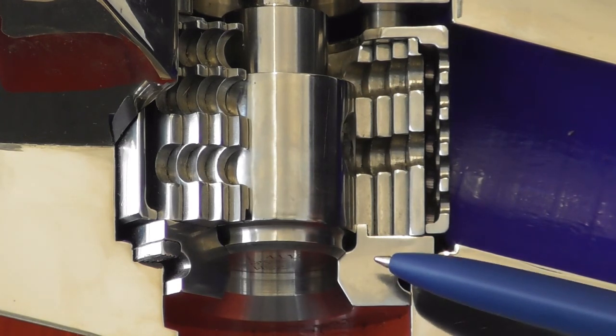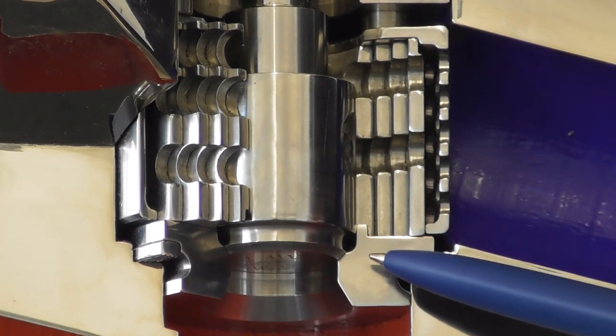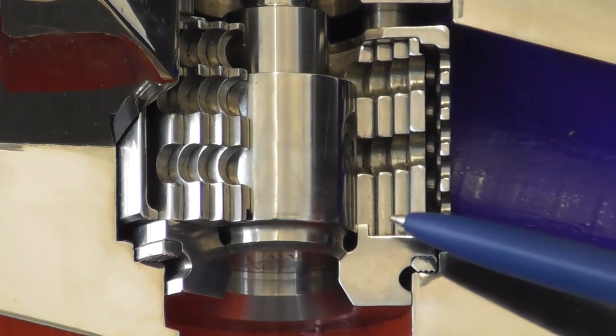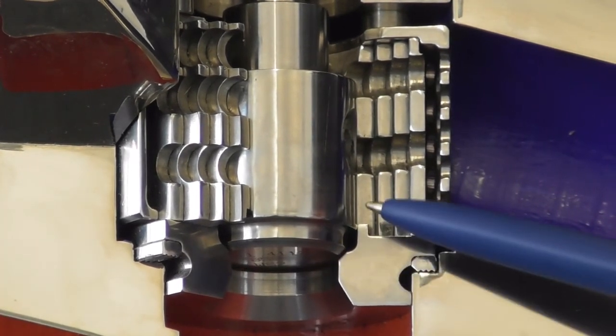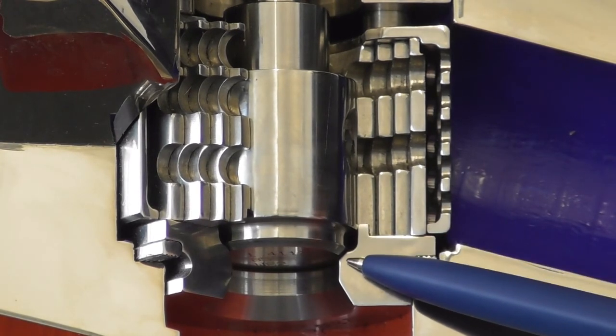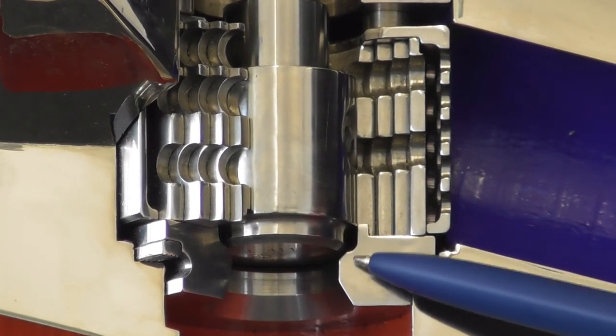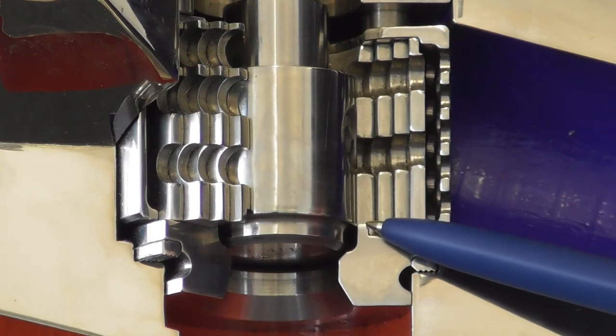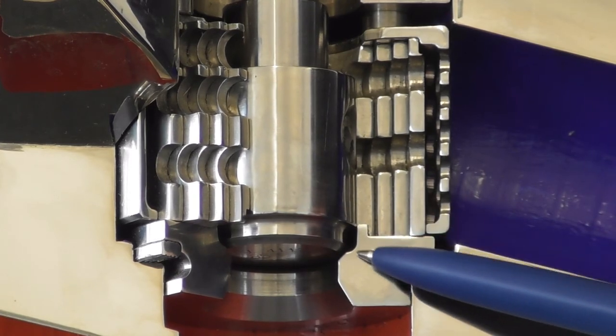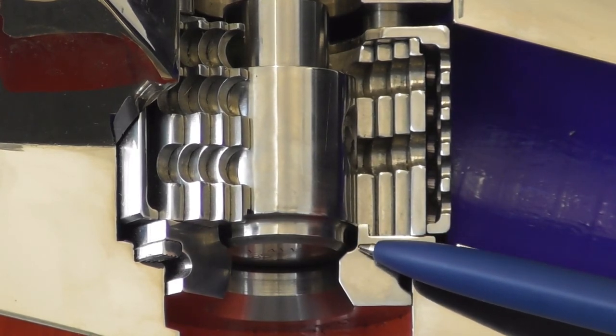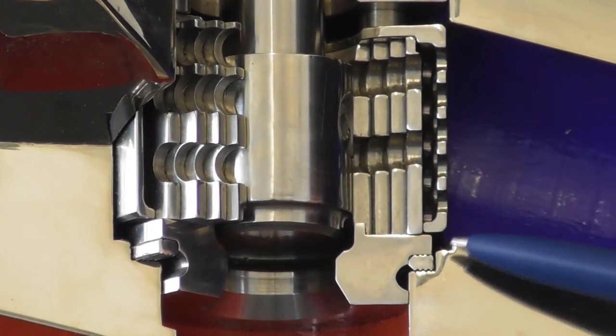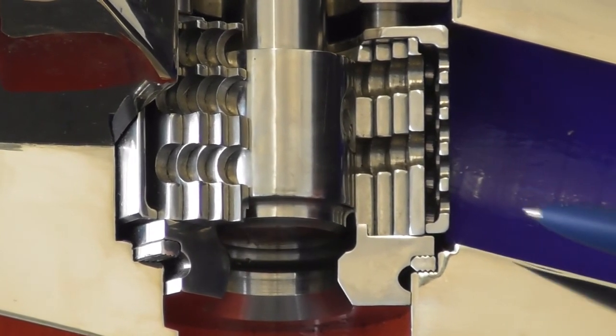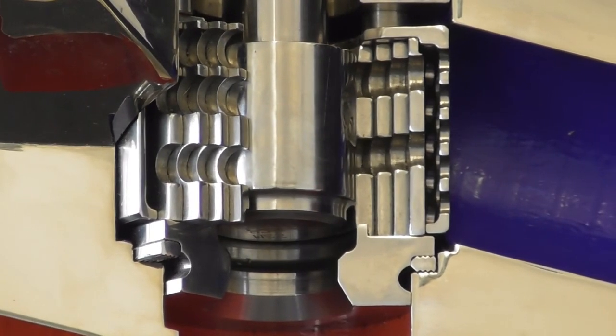The opening works in the same way only reverse. We are opening the valve so we lift off with the main valve plug here from the seat but we don't give the flow free by the control edge. After we reach the safety distance of two millimeters, the control edge gives the flow free and then we are here in the control position for the valve.